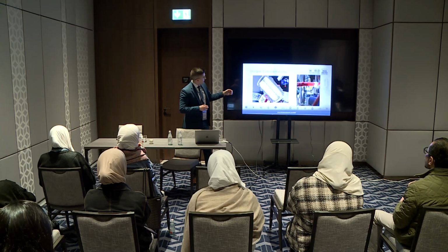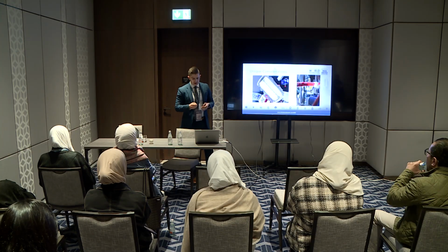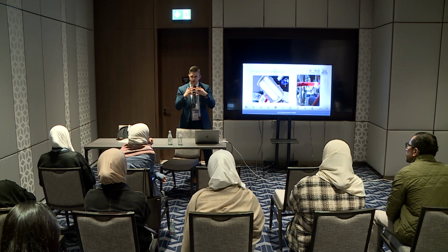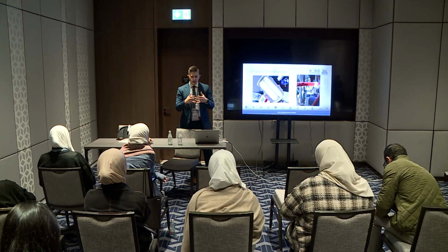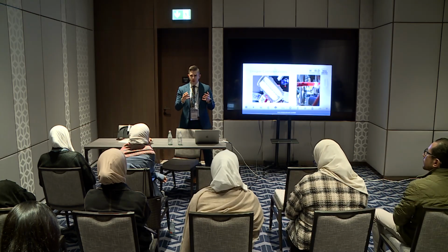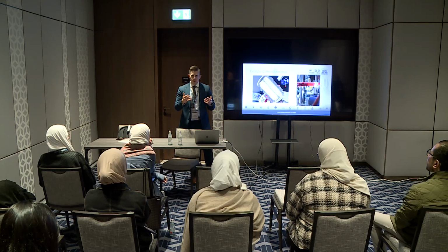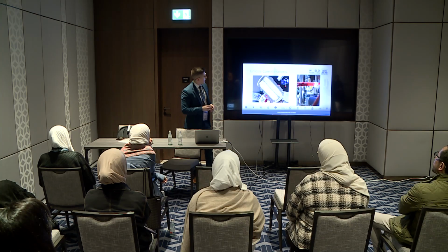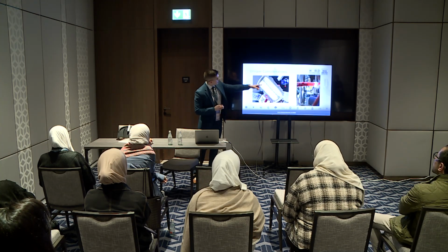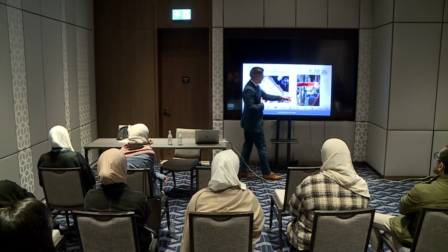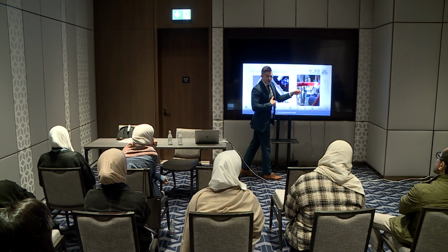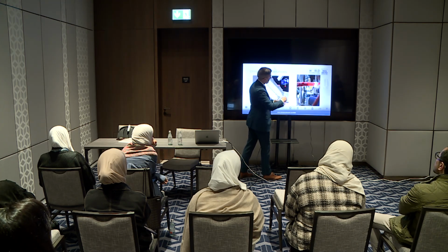I'll provide some more pictures in the next slide. But as blood passes through this, it's so densely packed, and you can imagine that if there are some deposits or something, it impairs how the blood flow passes across those structures. And then also, ECMO has many connectors. The picture over on this side is a connector. You can almost see here, this is coming off of the oxygenator, so off of the membrane.